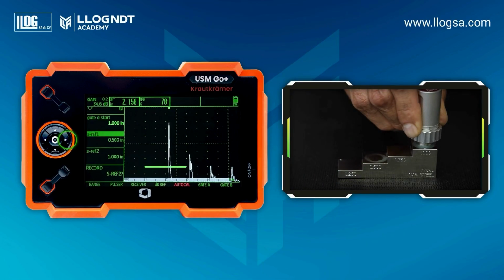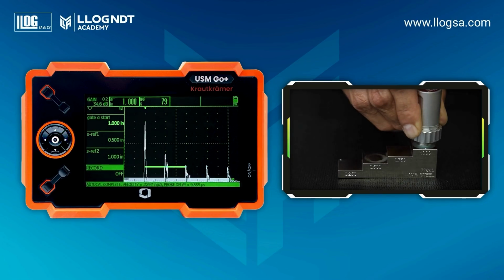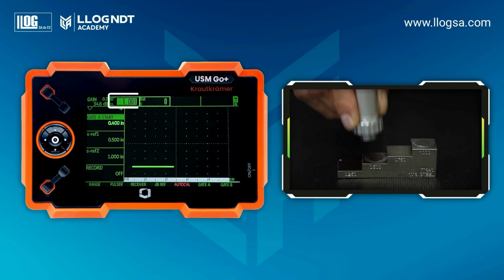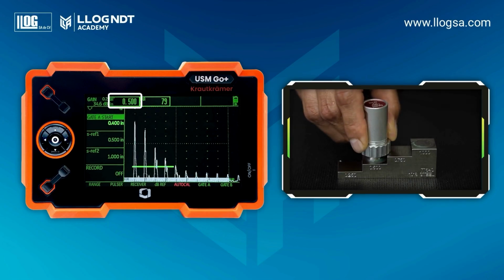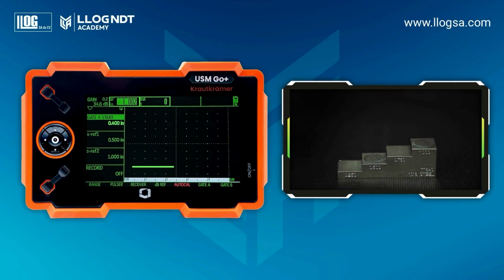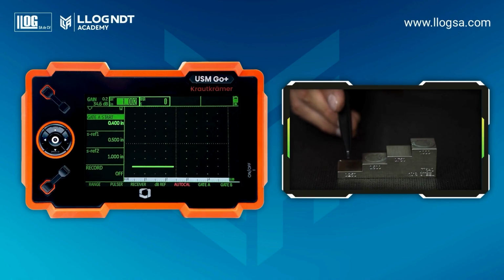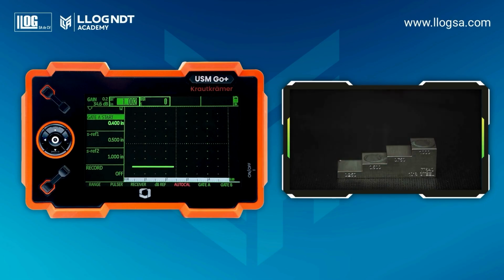To save the second reference, we press the right key in the record function. We then verify the reference values: 1 inch, and half an inch. Standardization can be performed with different references, either from a quarter to 3/4 of an inch, or from half an inch to 1 inch. This will depend on the minimum and maximum thicknesses to be inspected in order to select the references.